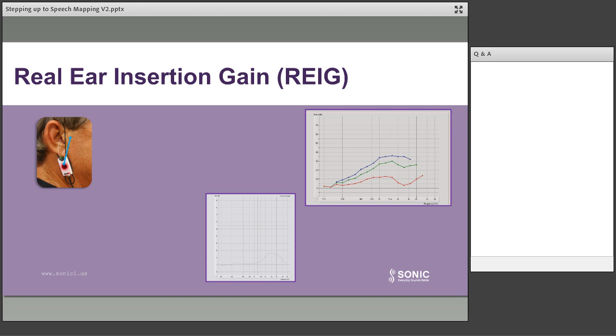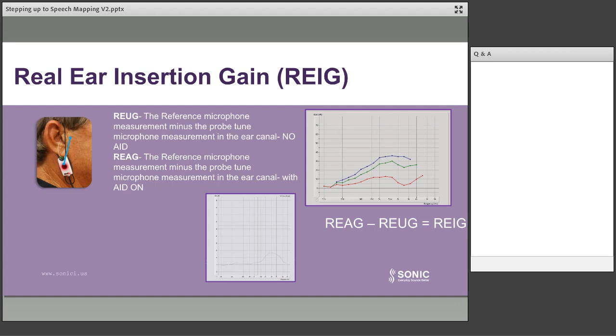So mostly though, and for a very long time, people have been using real ear insertion gain as their preferred verification method. And so we know that when we're doing real ear insertion gain measures, we're going to have the probe tube in the ear, and the reference microphone sitting outside the ear. First of all we do our unaided measure, our REUG measure, where we measure the sound level in the ear canal, and we take away the sound level from the reference microphone, and that gives us our unaided gain, which is this curve down the bottom. And then we put the hearing aid in and we turn it on and we perform the same test again. So put the sound through the speaker, measure what's in the ear canal, and take away what the level is at the reference microphone, and that gives us the REAG. We take both of those measures away from each other, and that gives us the real ear insertion gain, and those gain values are plotted on the graph.